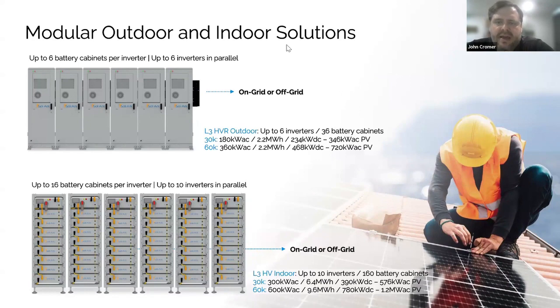The 60K being more powerful than the 30K, using 480 volt service instead of 208 volt service, can do a little bit more backup capability, a little bit larger solar array, the same kind of 2 MWh project size. So, this is very useful. You can do very large storage amounts in an outdoor ruggedized setting, where the project, for whatever reason, the shipping container just doesn't fit, whether it's ugly or tacky, or it's just not suited for the site.